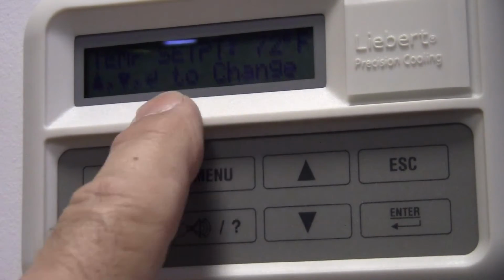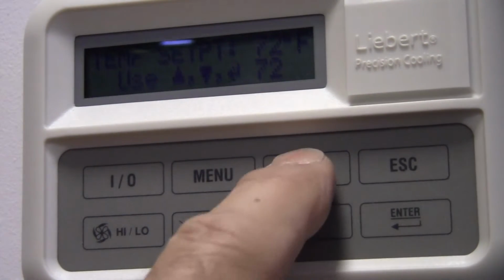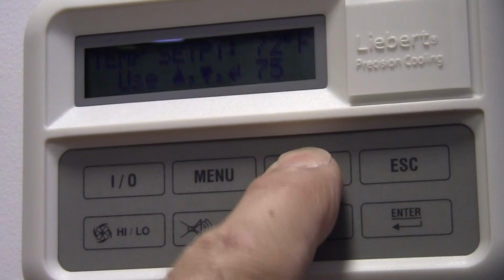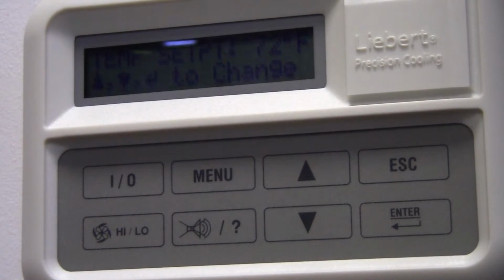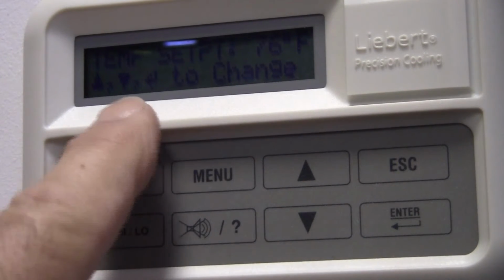And now set point 72, enter to change. Let's bring that 72 up to 76, enter. And there you go, you heard it cycle off immediately. So this absolutely looks like it's working fine. There should be a built-in time delay. Let's verify if that works.